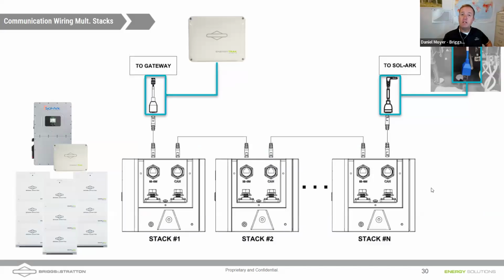If we're going to have multiple battery stacks on a single inverter, we're going to still come out of the CAN port up to the inverter, still out of the RS485, going up to the gateway, energy track gateway if you have it, and we're just going to simply daisy chain the Ethernet cables along.